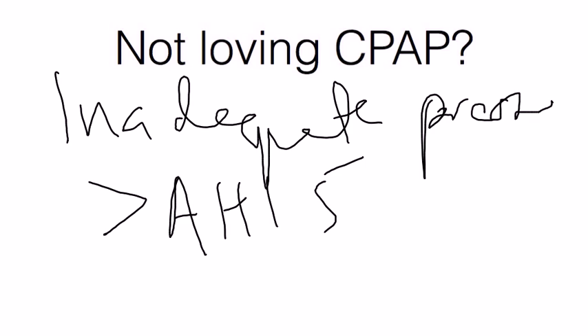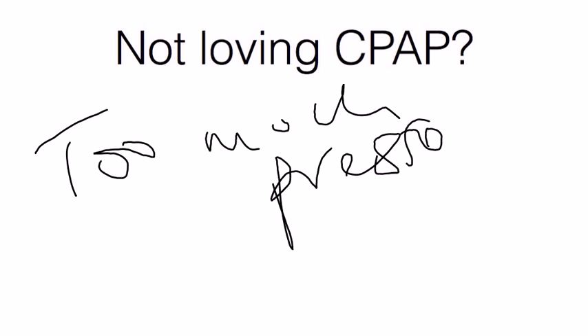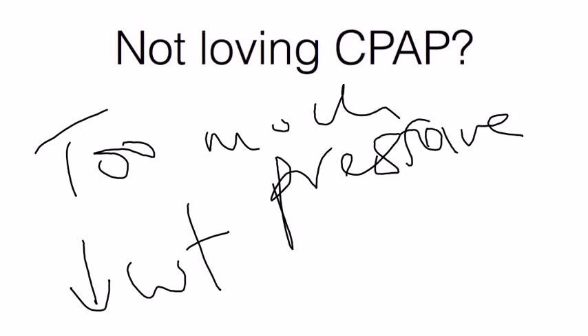On the flip side, you have patients who complain of too much pressure, and this may be due to various factors. One of them may be weight loss, so a drop in weight over time may cause the CPAP settings to be too high for the patient. The other thing is to confirm that the CPAP settings are what was indicated during the sleep study. It may be human error in keying the data into the machine at that point, and that may cause the pressure to be too high.